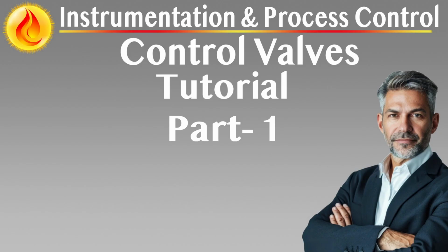Special designs, control valves, trim fouling, and self-cleaning considerations. Special trim designs, commonly used for noise or cavitation control, typically incorporate small passages to reduce fluid pressure gradually. These narrow paths introduce fouling risk under abnormal operating conditions during commissioning or while flushing the system. Each application must be evaluated for fouling potential across all operating scenarios, including startup and emergency states. Where such trims are necessary, preference must be given to self-cleaning designs. These expand passageways as the valve opens, reducing blockage risk.